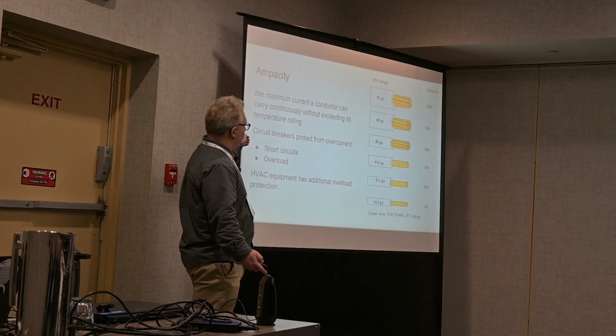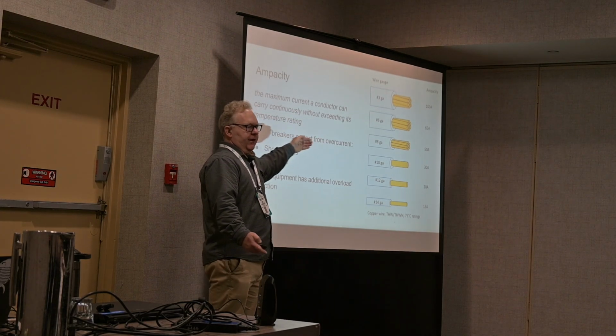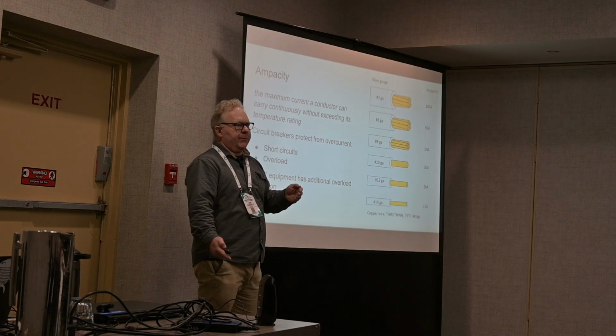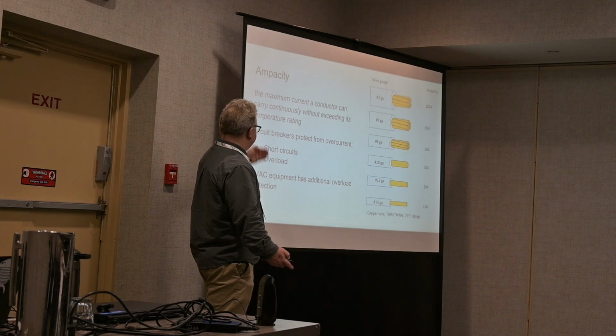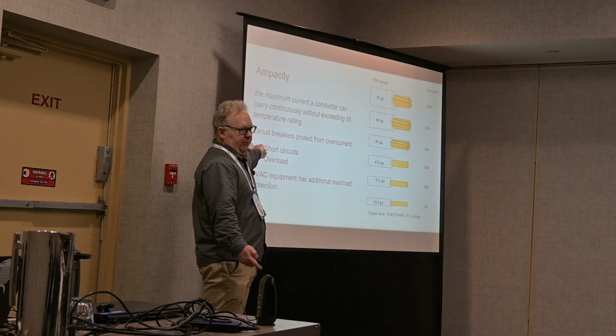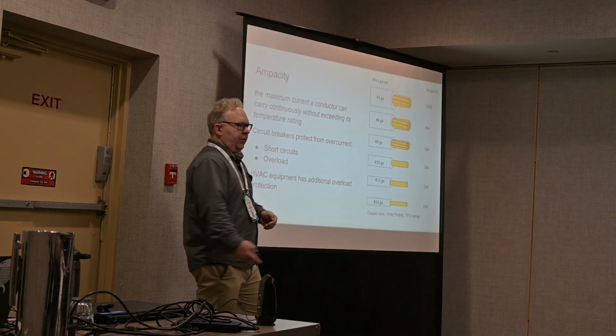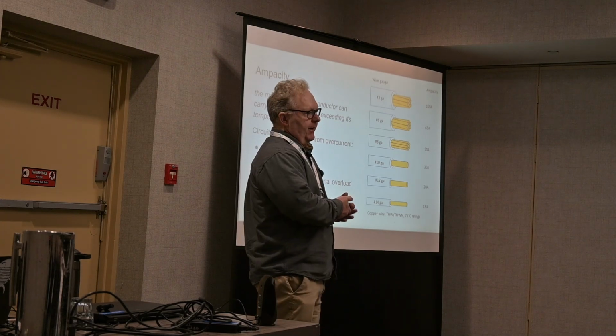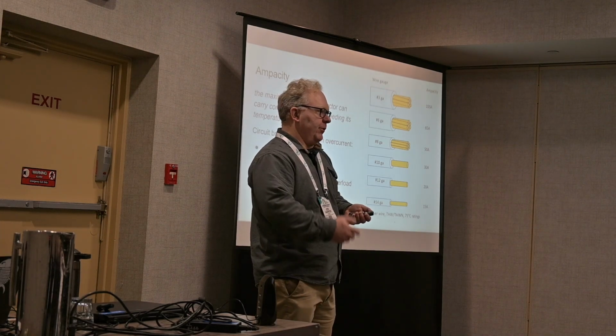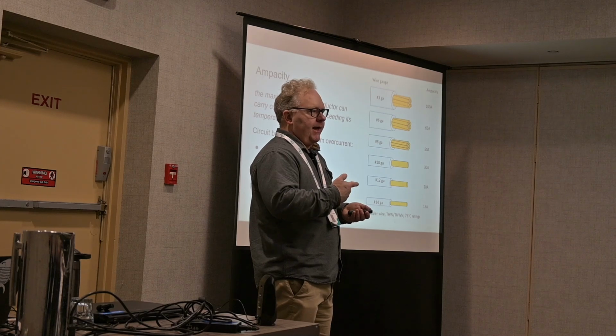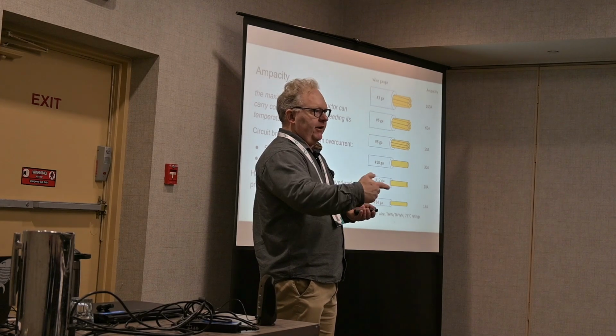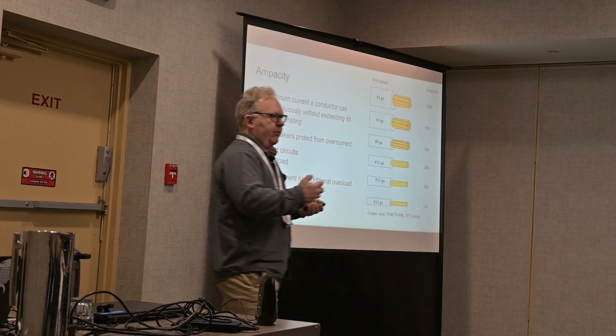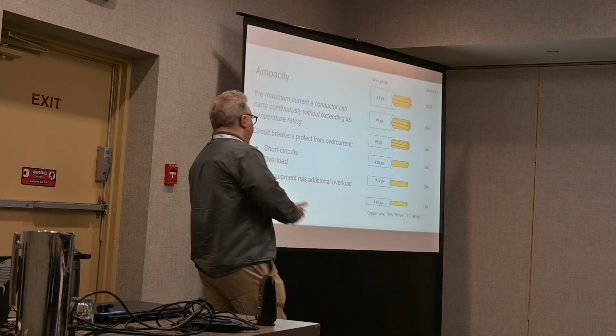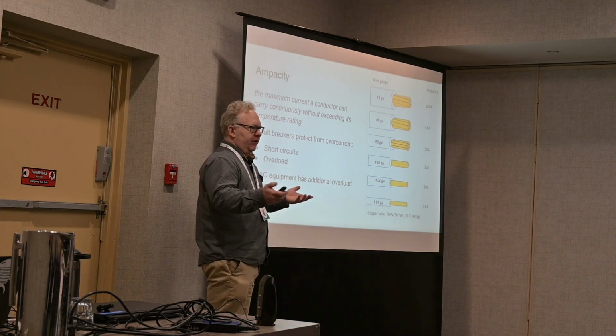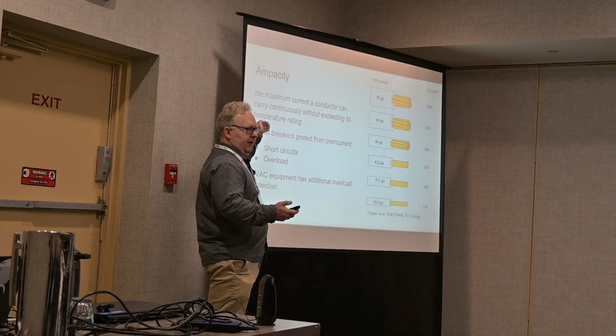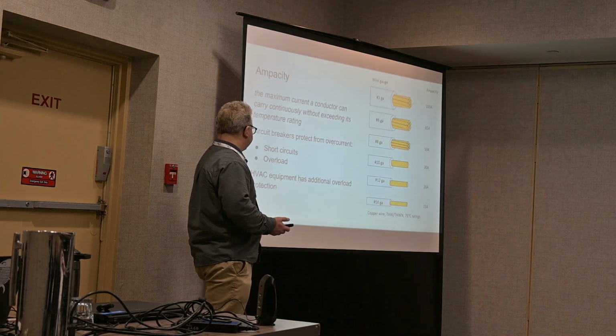Circuit breakers are paired with our conductors, and what they'll do is trip if that safe current is exceeded. And that can happen in two main conditions. One is short circuits. That would be an example of, I'm not paying attention to what I'm doing, I put a screw through a wire, and suddenly I've connected my hot conductor to my neutral. A massive amount of current can flow, and if that continued to flow, it could start a fire, but the breaker immediately trips and shuts that down.